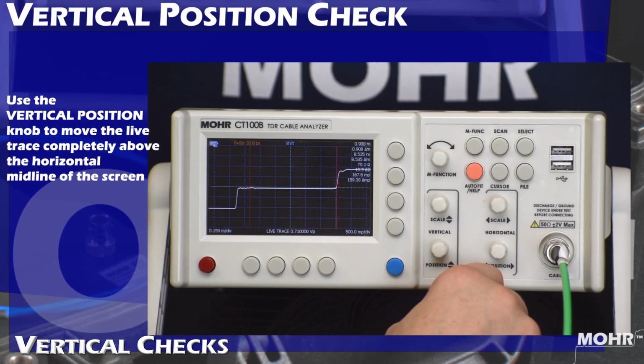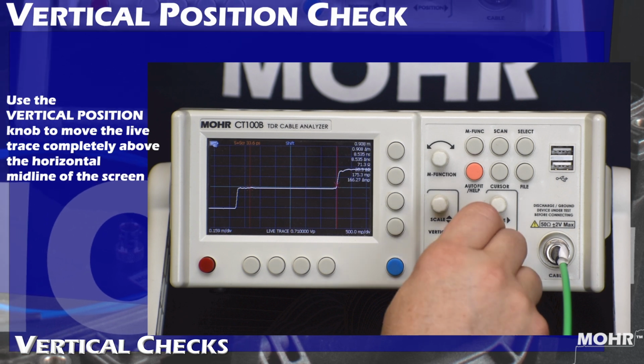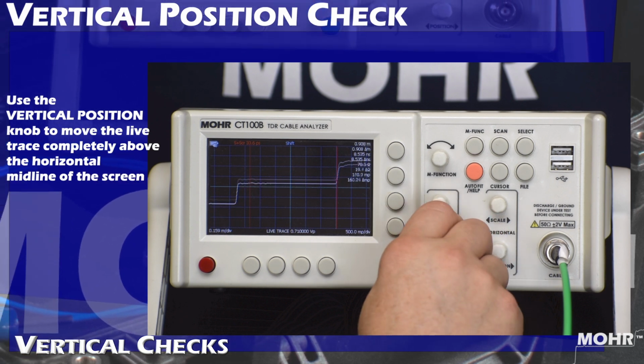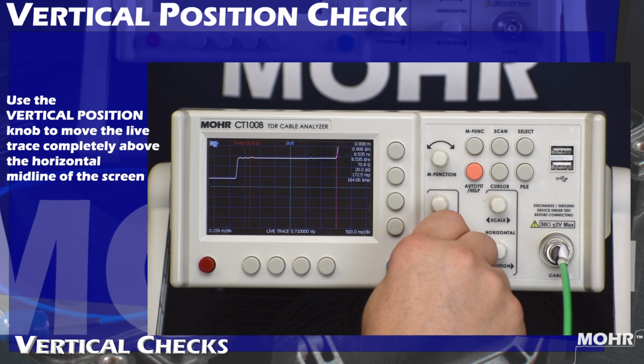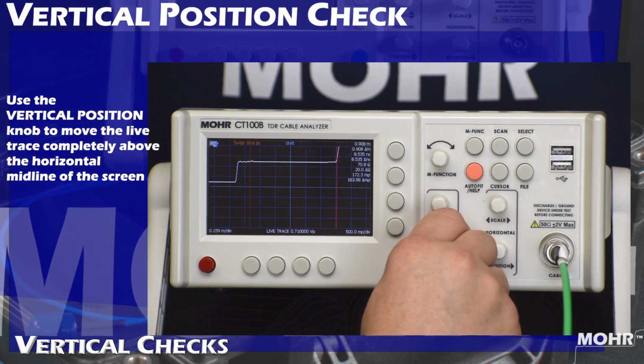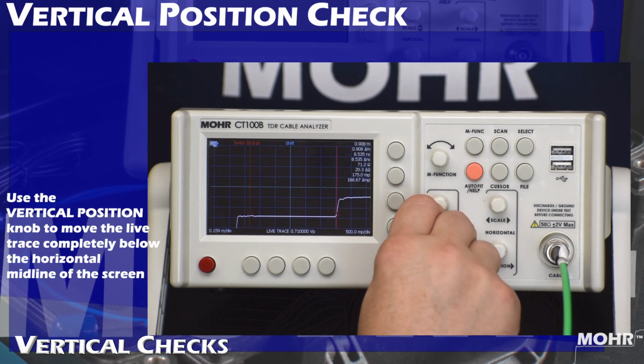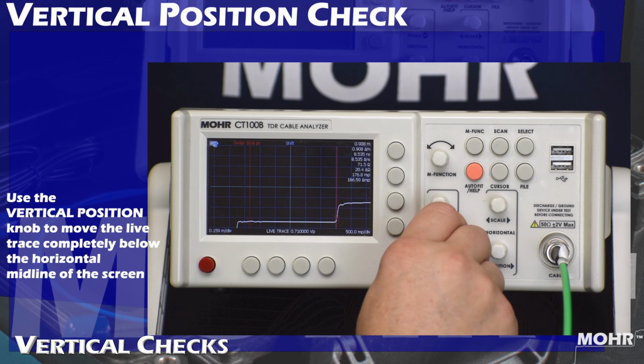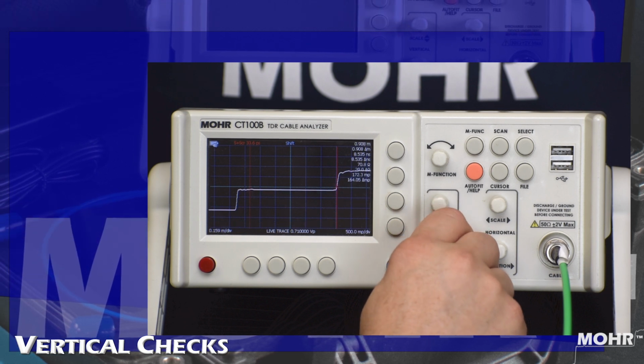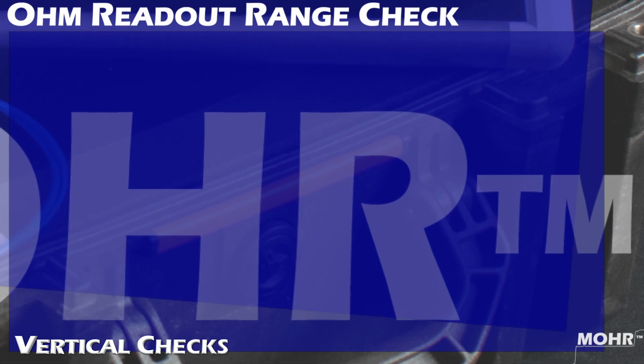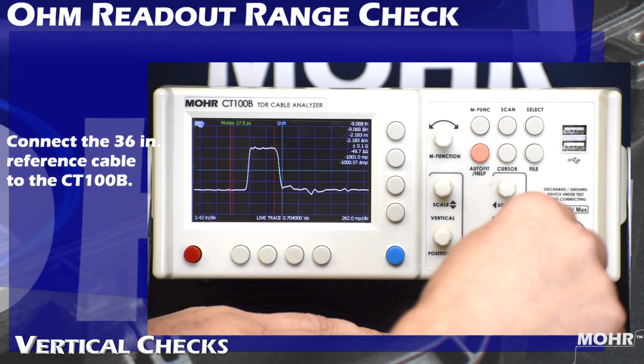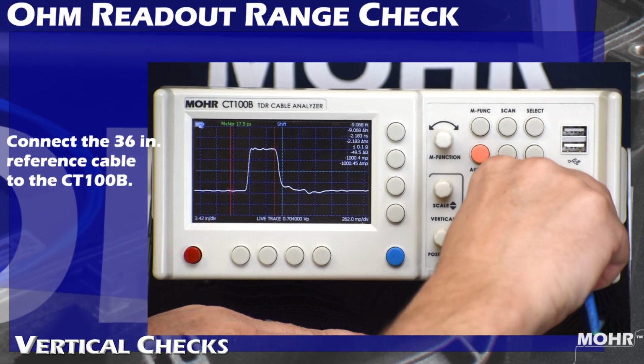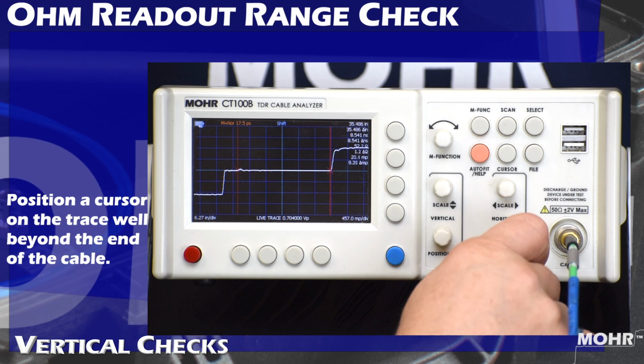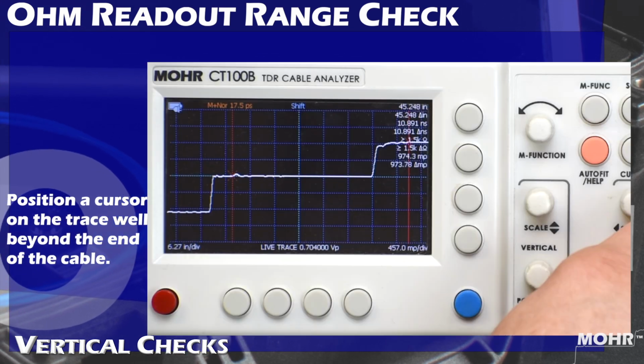Use the vertical position knob to move the live trace completely above the horizontal midline of the screen, and then use the vertical position knob to move the live trace completely below the horizontal midline of the screen. For ohm readout range check, connect a 36-inch reference cable to the CT100B. Position a cursor on the trace well beyond the end of the cable.